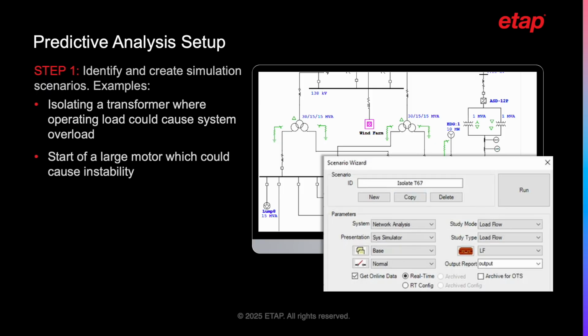Leveraging the intelligence of ETAP's predictive analysis tools, engineers can first identify and create simulation scenarios for all conditions that need to be continuously evaluated, as they may cause a significant impact on the operation. Examples of such actions can include isolating a transformer where the operating load may cause an overload in the system.